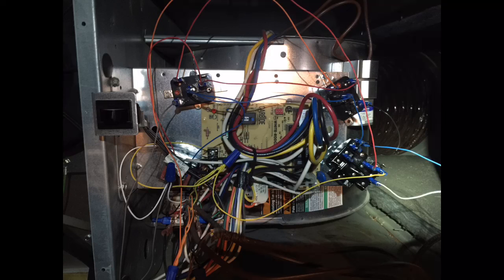My heating guy said, in our furnaces we just use the W terminal in common to run the humidifier. Yes, that is not a bad option, other than the potential for dragging down the transformer power. And I prefer to use isolation relays and a second transformer so that we don't crisscross.